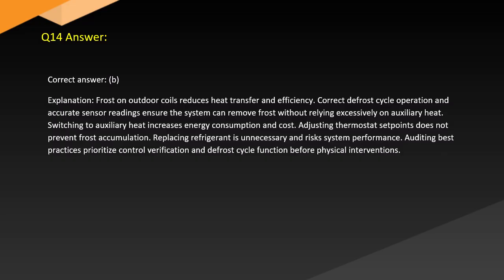Answer. Correct answer, B. Explanation. Frost on outdoor coils reduces heat transfer and efficiency. Correct defrost cycle operation and accurate sensor readings ensure the system can remove frost without relying excessively on auxiliary heat. Switching to auxiliary heat increases energy consumption and cost. Adjusting thermostat set points does not prevent frost accumulation. Replacing refrigerant is unnecessary and risks system performance. Auditing best practices prioritize control verification and defrost cycle function before physical interventions.